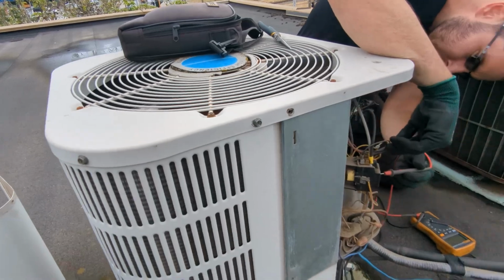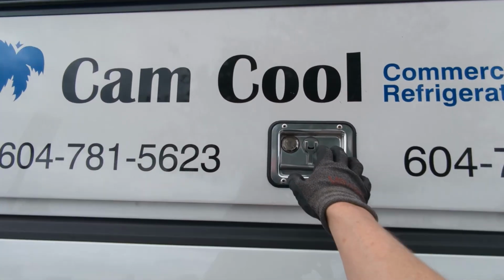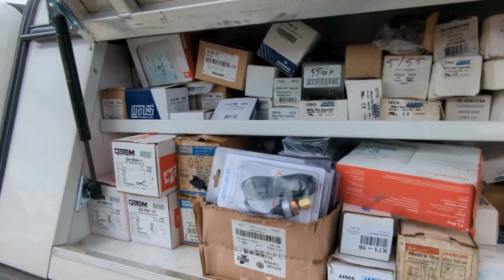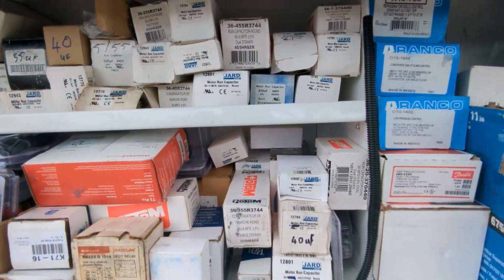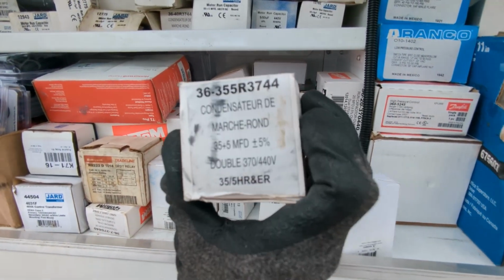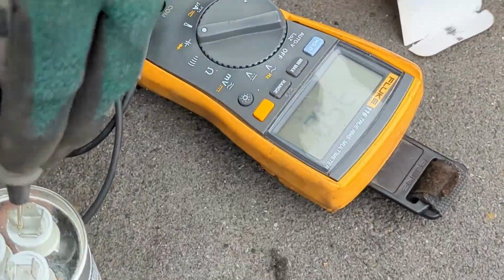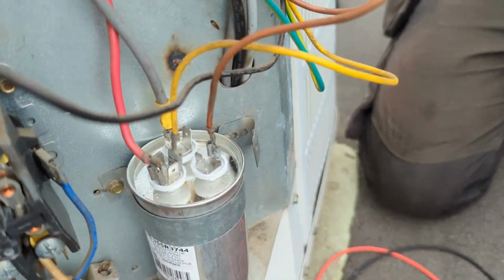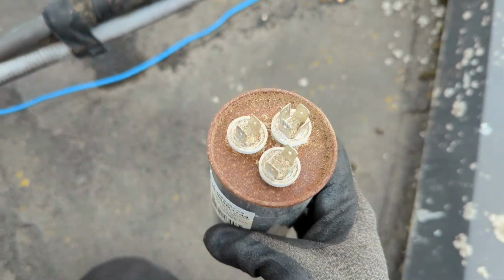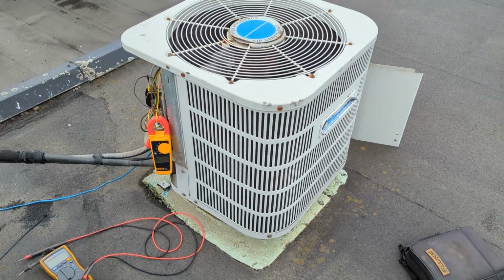What we found was the fan capacitor was busted, so we replaced it. The fan started up right away, but the compressor did not start up right away, and it's because of that internal overload. So this compressor could either start up today after it's cooled down, sometimes they take within an hour to 6 hours to cool down and restart, or it could be completely dead.